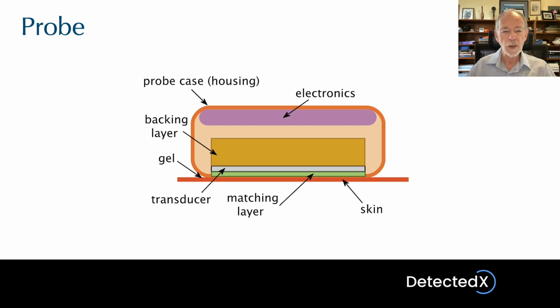You'll see that in front of the transducer material we have what I've shown as a green material, and this is labelled matching layer. The purpose of this is to match the transducer to the tissue to improve the free flow of energy between the transducer and the patient's tissue. This is needed because the transducer material is very different to tissues, and therefore it has a very different acoustic impedance. So basically the matching layer acts as a kind of translator between the transducer and the tissues. It operates both in transmitting and receiving to minimize the effect of the acoustic impedance difference between the transducer and the tissues.